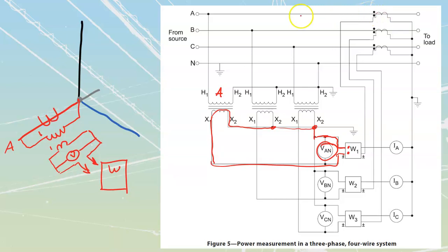I see that I've got the dotted end connected over to the A, so we'll make that connection over there. Then if I trace this down, I'm going to go through my watt meter - that's the ammeter section of the watt meter. Then it comes back, goes through another ammeter, and ties back down to what we'd refer to as our common, or a Y point for that system.